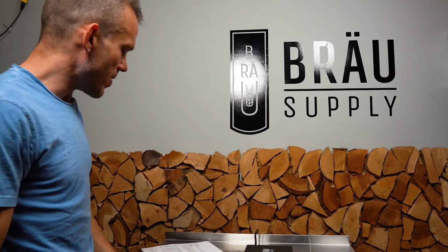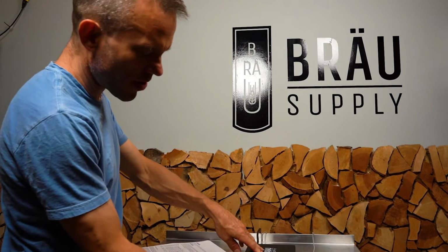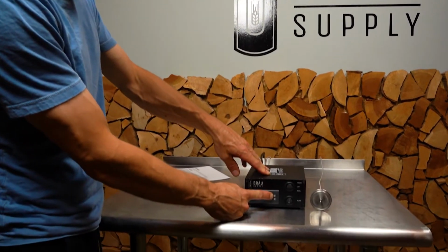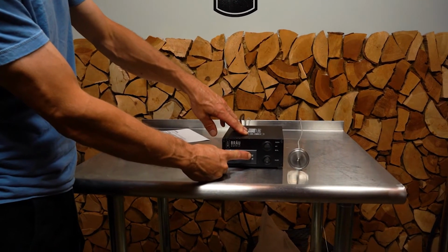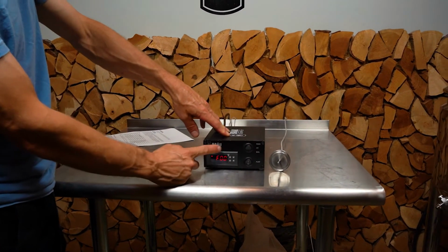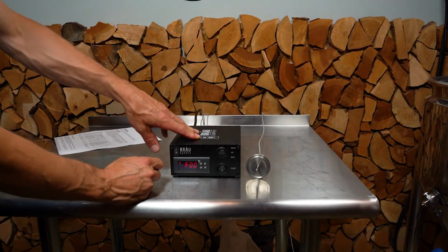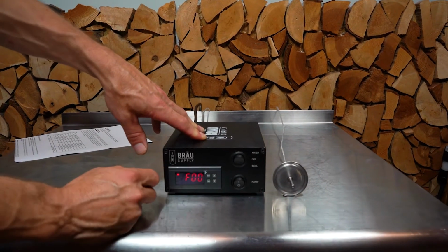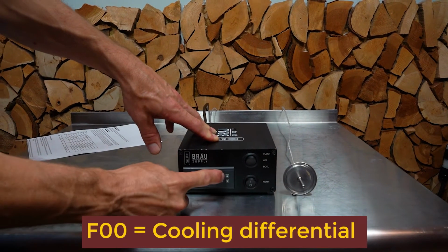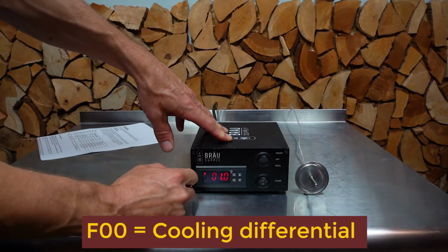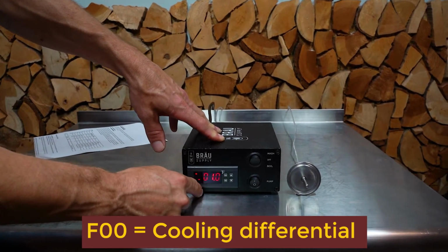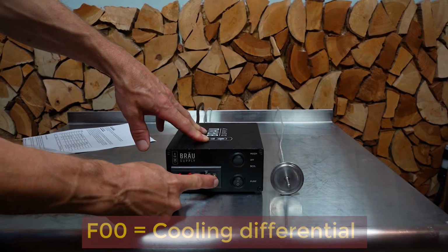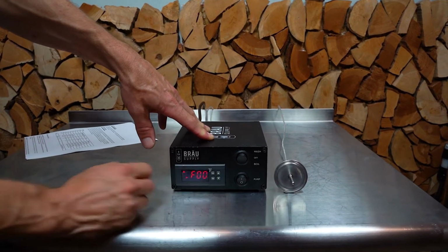Now what I want to talk about is the control panels that are inside this unit. So I'm pressing the set button, and you press it until you see the display change. It says F00. And F00 is cooling differential. So if you want to change that, or if that matters, it's set to 1 degree right now. You can up and down with the arrows and then press set again.